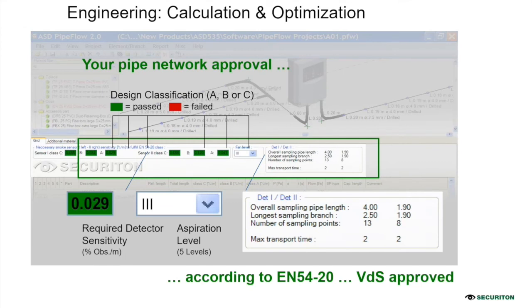The fulfillment is checked for all the classes, and when the design is confirmed, the software gives a green light. If it is red, then we need to redesign the system as per the limits. The software complies with NFPA, and calculations can be done based on both NFPA and EN. I'm talking about the calculation of the software, and the software is not different, it's the same software.